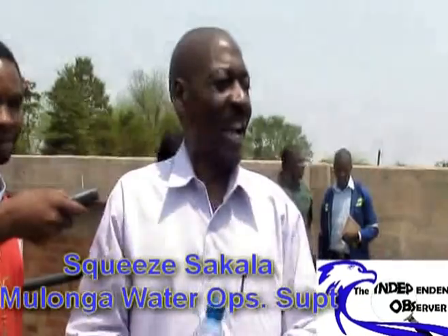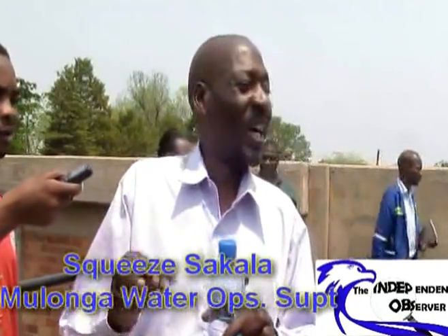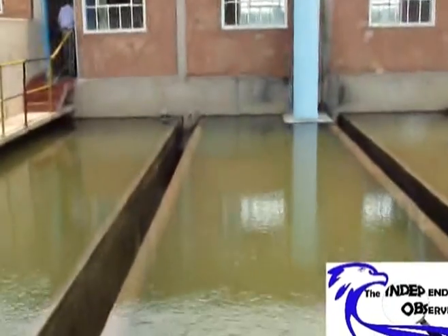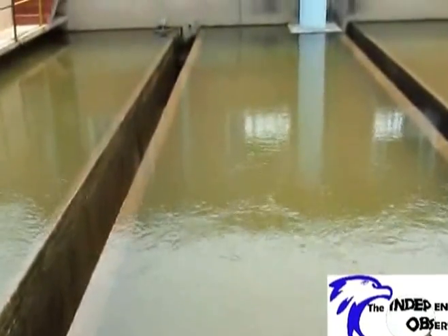The treating process continues. Produced into the filter bed, it passes through the filtering media, which is the sand. Now, the filter bed is about 1.5 meters deep, of which 1 meter is filtering media, which consists of coarse sand, medium sand, and fine sand. So the total composition is 1 meter from the bottom of each filter bed.